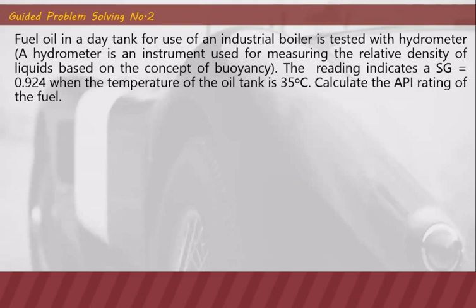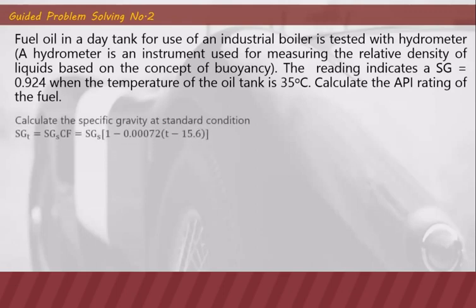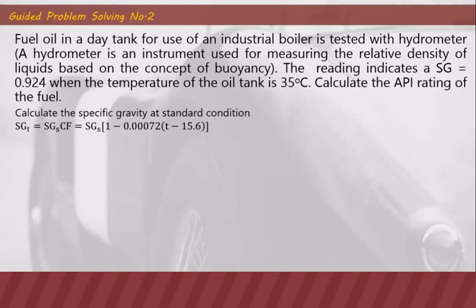Guided problem solving number two: fuel oil in a day tank for an industrial boiler is tested with a hydrometer — an instrument used for measuring the relative density of liquids based on buoyancy. The reading indicates a specific gravity of 0.924 when the oil temperature is 35°C. We need to calculate the API rating. Since the SG of 0.924 is measured at a particular temperature, it is SGT (not SGS), so we must first find SGS using the correction factor, then compute the API rating.